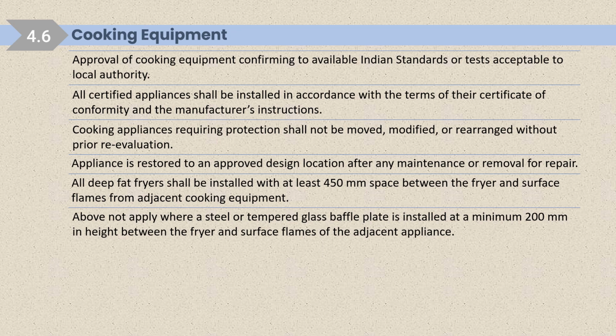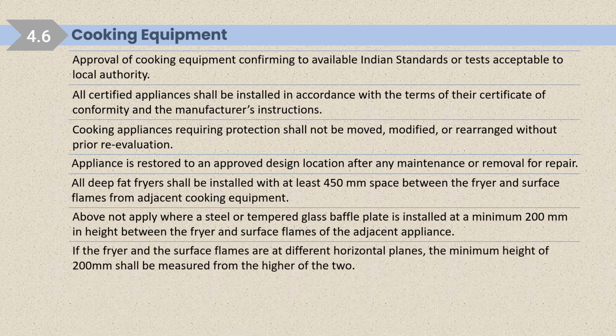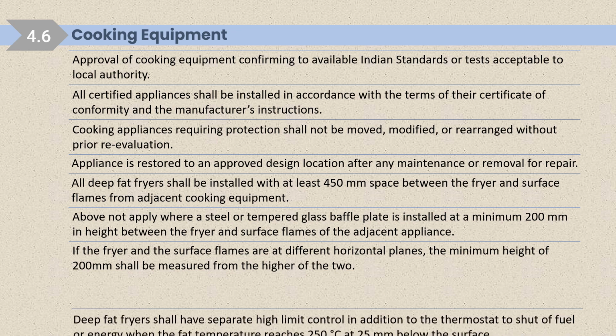The above does not apply where a steel or tempered glass baffle plate is installed. Suppose it is not feasible to maintain the gap of 450 mm. In that case, we need to provide a baffle plate at a minimum 200 mm in height between the fryer and surface flame of the adjacent appliance. If the fryer and the surface flames are at different horizontal planes, suppose one is above and the second one is kept on a lower surface, then the minimum height of 200 mm shall be measured from the higher of the two.